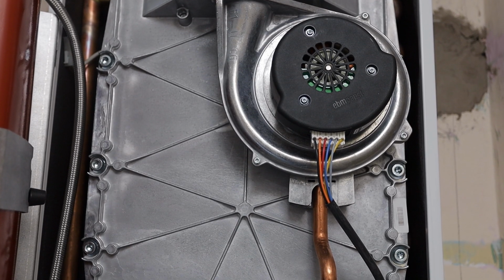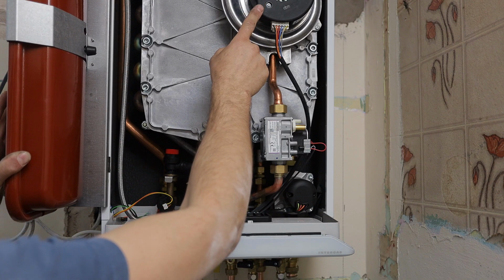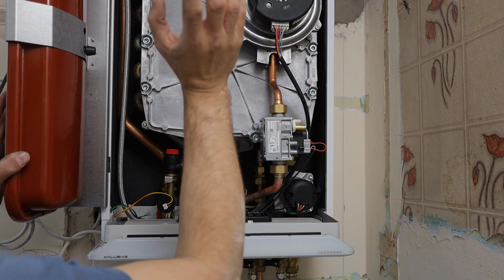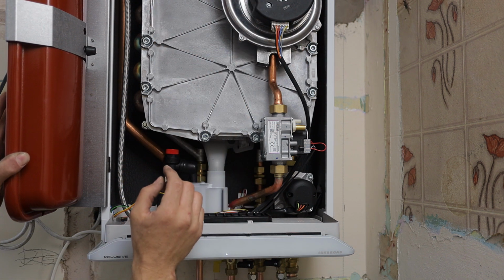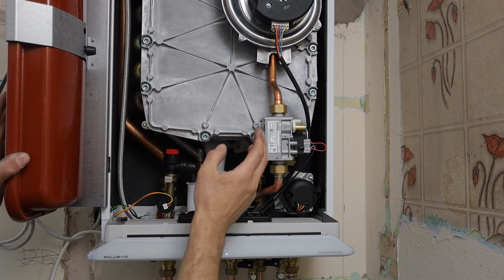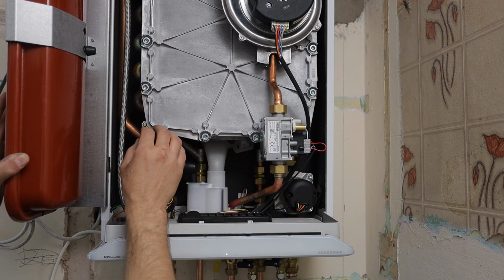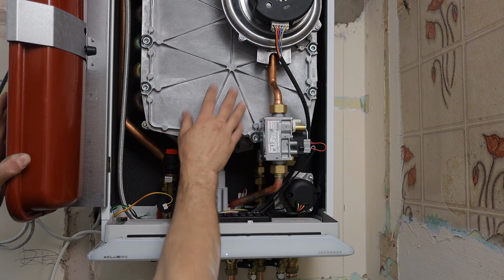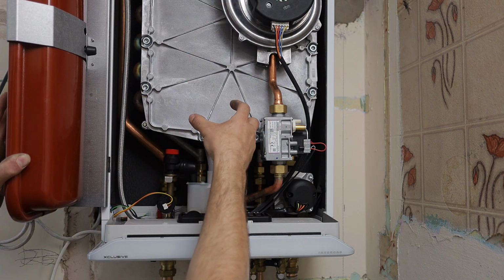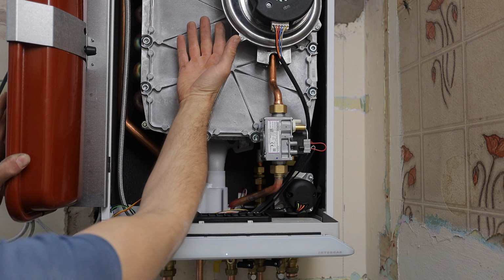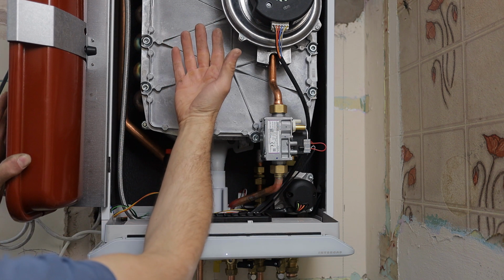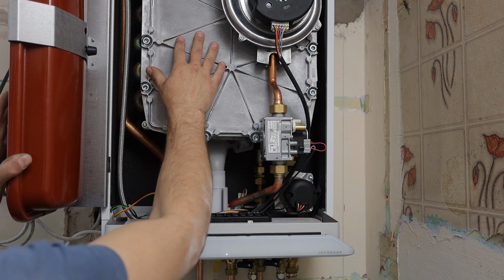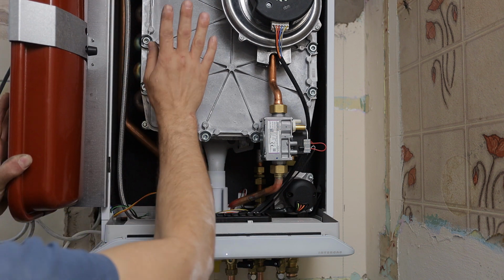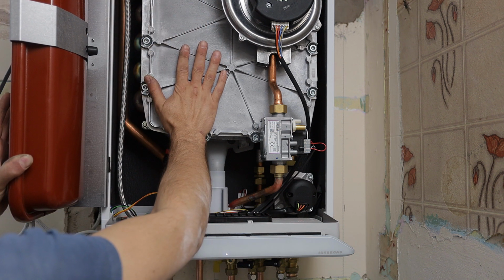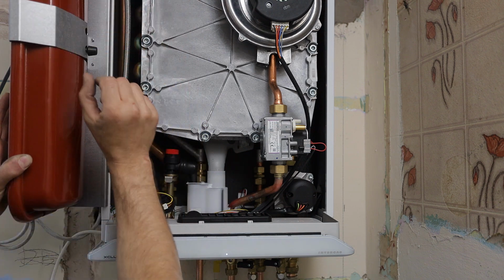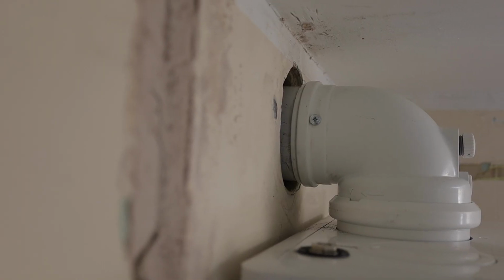This is a 325 volts DC fan, and I was told by Intergas that they had to make it a high voltage fan to be able to allow for really low modulation, as this boiler goes down to 3.6 kilowatts. The manifold on this boiler was moved from the front flue manifold to the back, and the heat exchanger was moved slightly forward, because on the other versions the heat exchanger sits right at the back, and because it's slightly forward, now when you put the flue elbow on top, you actually don't go with the flue into the wall.